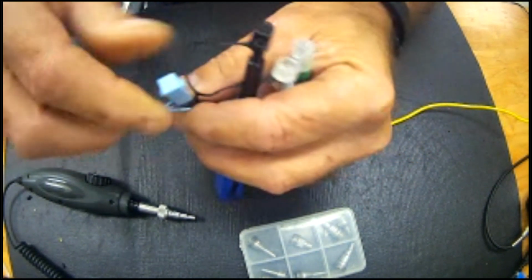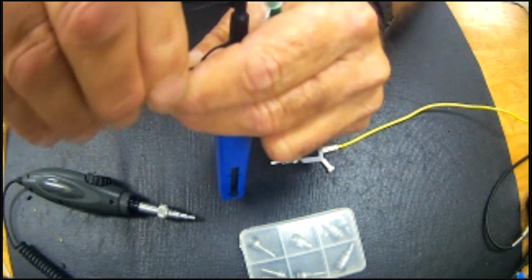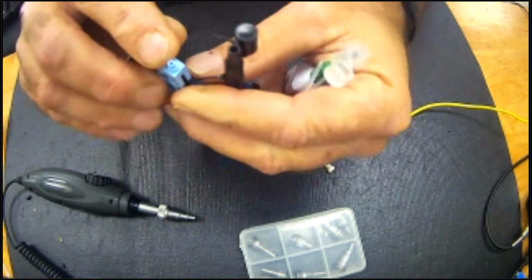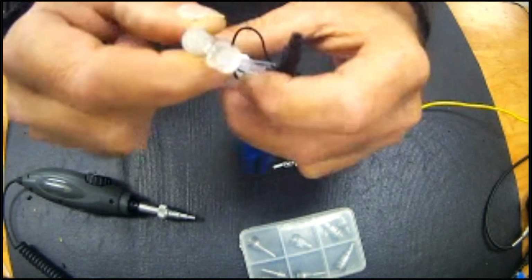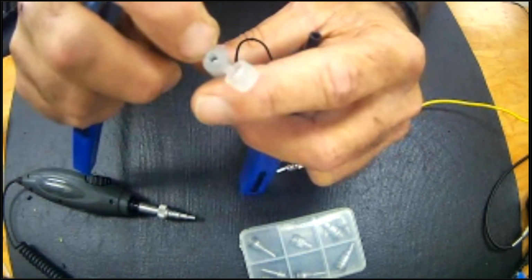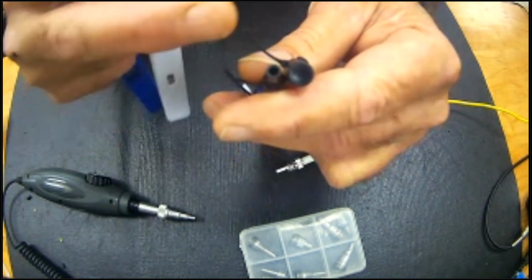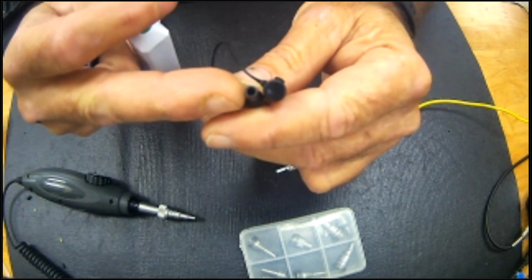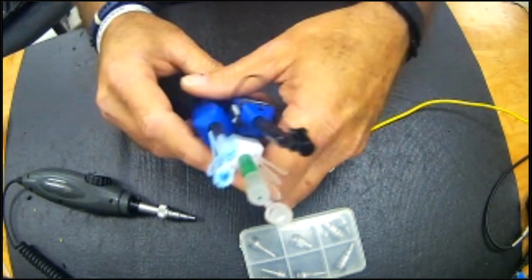In this case, I'm holding 3 in my hand. And yes, you must have 3. So you've got your LC, which is your 1.25. That's Lima Charlie. Then you've got your SC, ST, FC, Frank, Charlie, Sam, Tom, etc. That's your 2.5 millimeter. Then you've got your 2 millimeter, that's your SMPTE. You need to own all of them basically in order to service and maintain fiber.